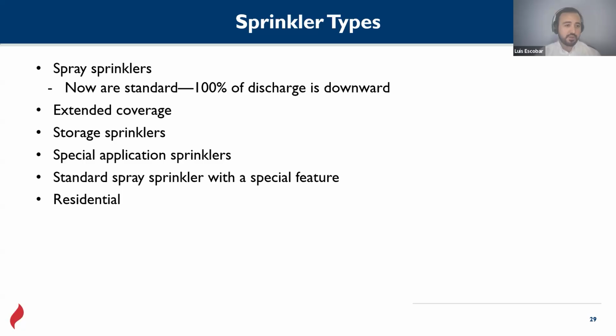The next type of sprinklers would be extended coverage. These sprinklers are designed so they can spread water more horizontally than the standard ones. Storage sprinklers, probably sprinklers that can be installed between the racks. Special application sprinklers, we're going to go over that in a couple of slides. Standard spray sprinklers with special features, for example, if they are corrosion resistant. Maybe if the application is to protect a canopy outdoors with a dry system, we saw that those systems tend to be in corrosive environments. So it could be a corrosion resistant sprinkler with a polyethylene cover, right? And residential.